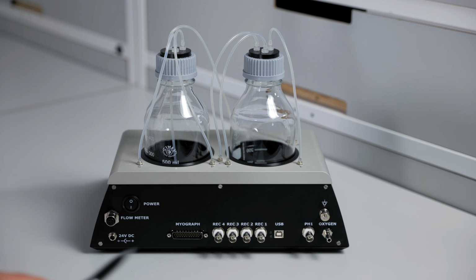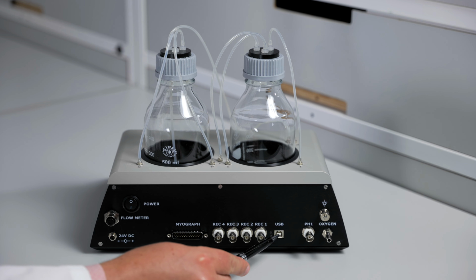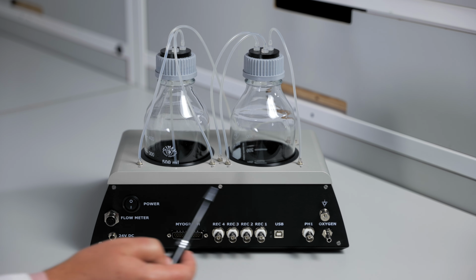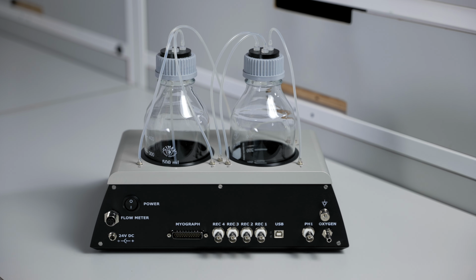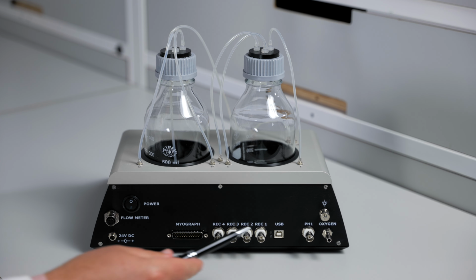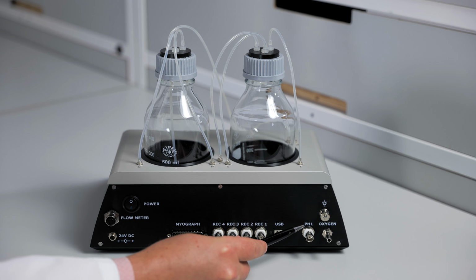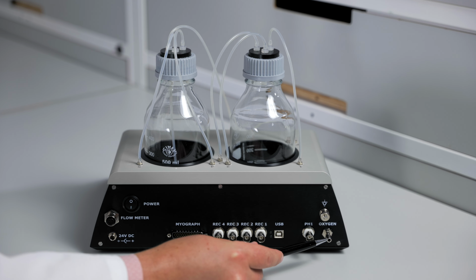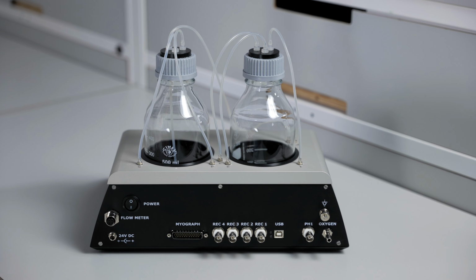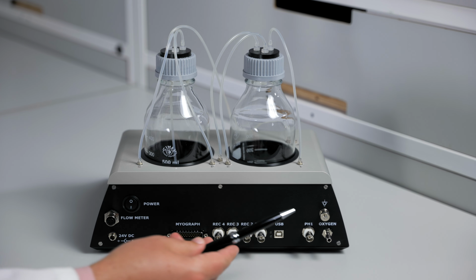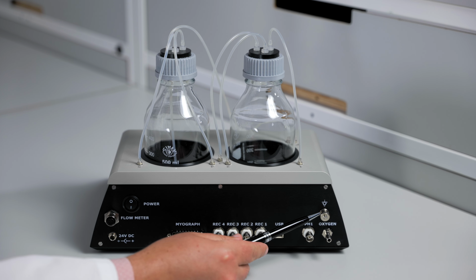There's a connection for a USB cable, which will go to the computer and will send all the data to the MyoView software. There's a connection for an optional pH meter. This is the port that will connect to your gas tank and drive pressures and flow through your vessel. And finally, there's a ground port to eliminate any electrical noise.